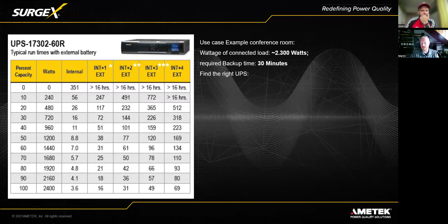We would choose the next value up from the load, so we'd jump into the watts section and choose 2400 watts, since it's slightly higher than the 2300 watts we need. As a second step, we'd look at the internal chart, which shows the runtime on internal batteries — in this case, 3.6 minutes.